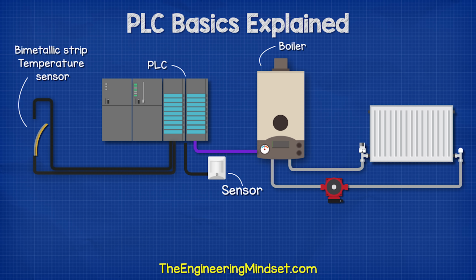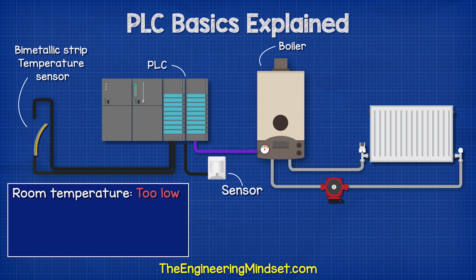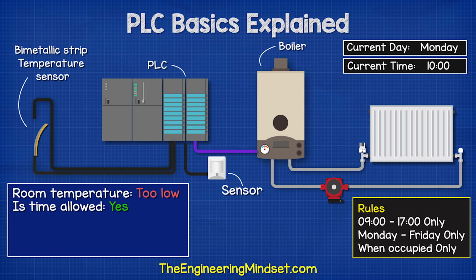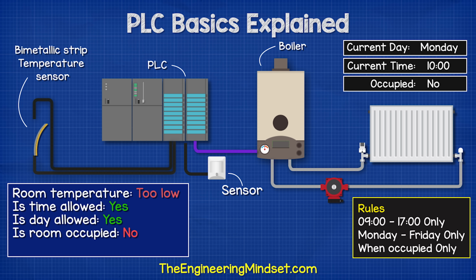We can then add extra functions and inputs, for example, a motion sensor on the input. The thermostat tells the PLC the room is too cold. The PLC will check the time to ensure it is allowed to turn the boiler on, and now it can also check to see if the room is occupied. For example, there could be a public holiday that isn't listed on the calendar.